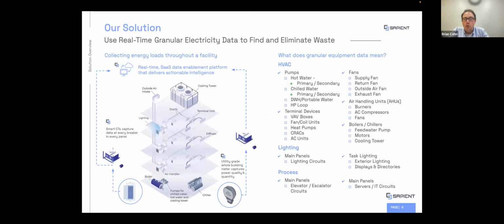On a much larger scale, we can take a look at when things are running. What we've found is most facilities, while designed to be commissioned, had someone leave a drive in bypass or override a lighting system, and next thing you know those things are running continuously 24/7. A lot of this becomes sequence-of-operations type changes that cause significant reductions in energy.